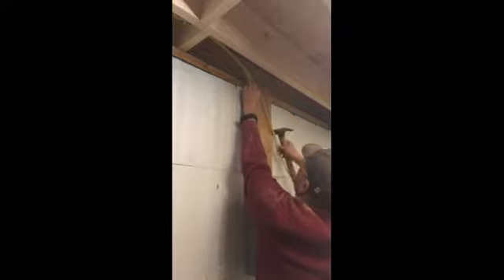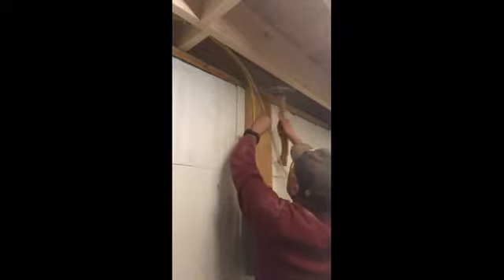So essentially, if you plan on having a ceiling in your basement, it's best to drill through the floor joists in your basement to hide the wires up into the joists. You may want to use a 1.5 inch bit, as you can run trunk lines of wire, usually up to 6 per hole, and then you can have 6 separate circuits run to your panel box.